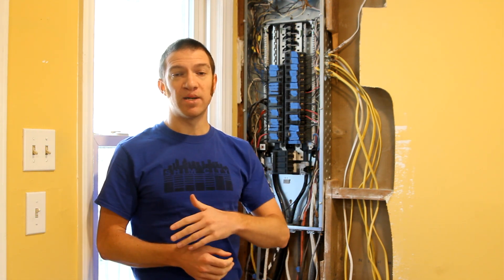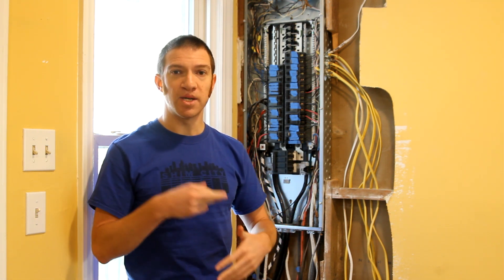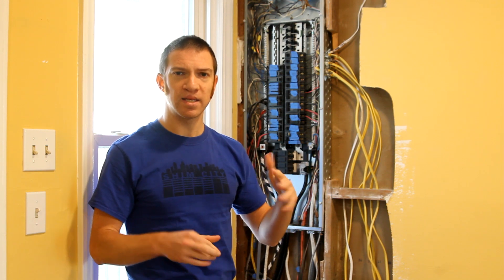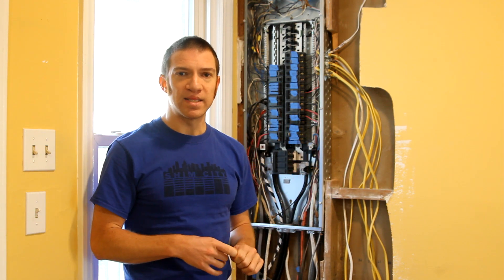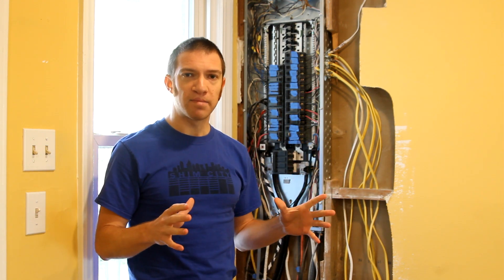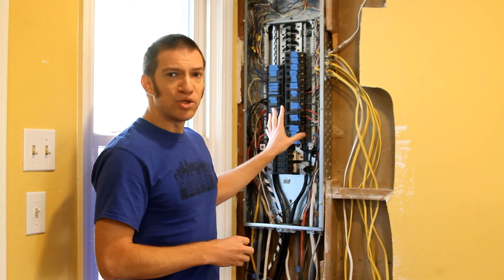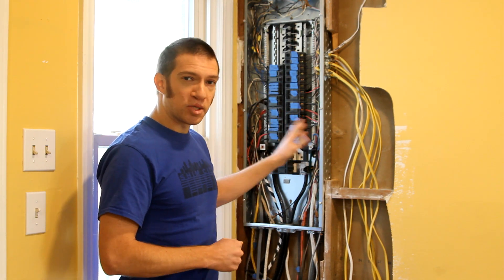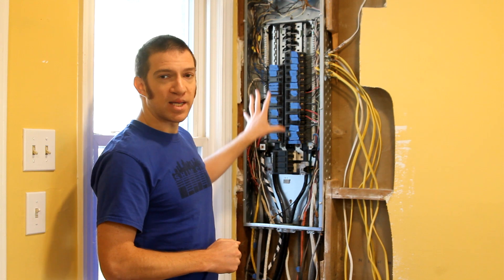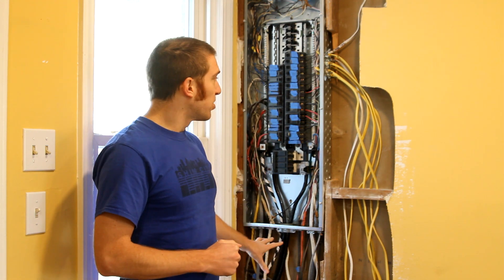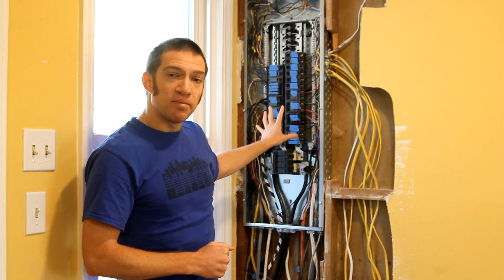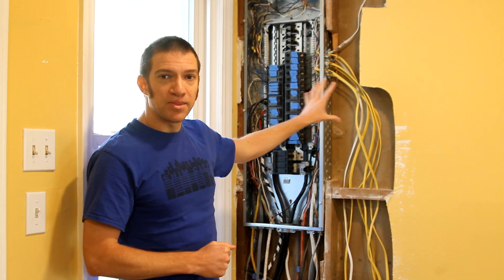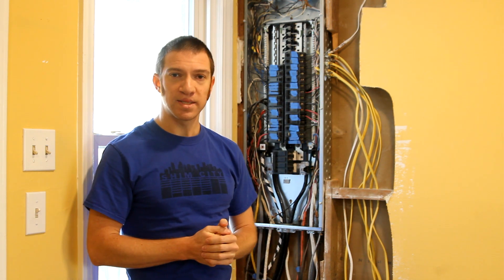If your panel is outside, then you'll have sort of the same considerations, except you'll also be thinking about the siding, as well as making sure that you can keep that entire box encapsulated properly. When you're buying a new panel, think about where all the wires are going to be coming out of the box. For example, ours had limited number of options for the ports at the top and the bottom, so we ended up using ports out the side to finish up all the rest of the circuits that we needed.